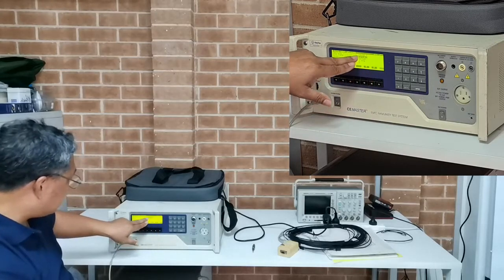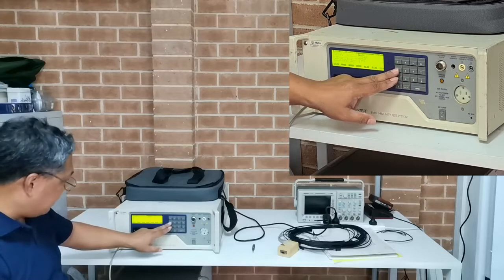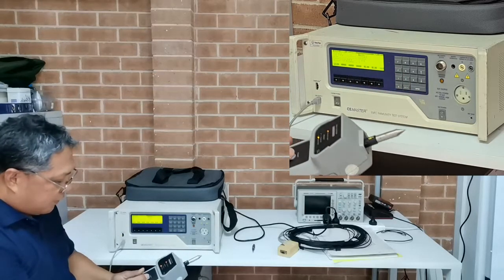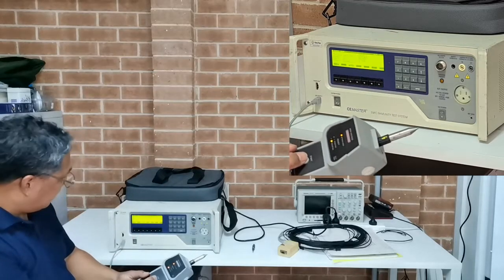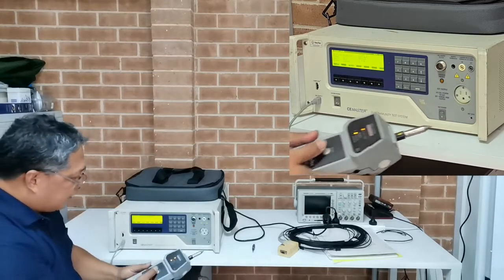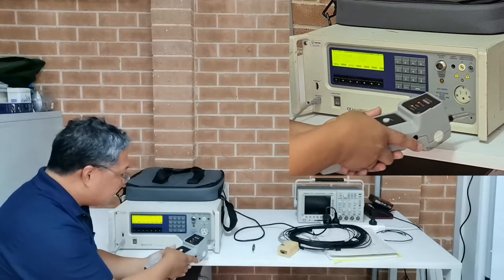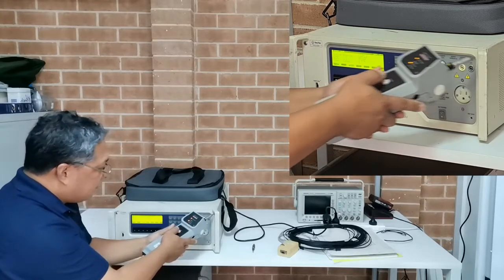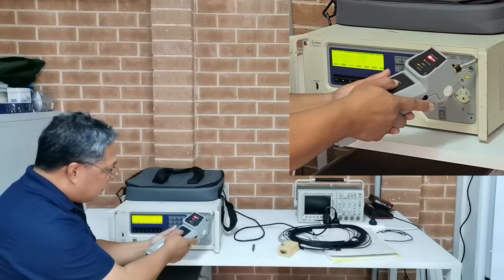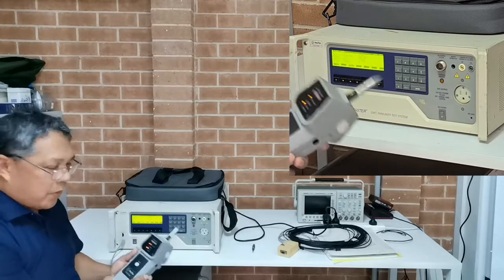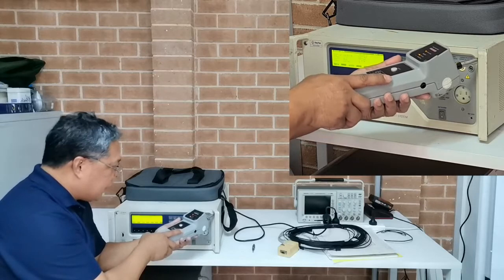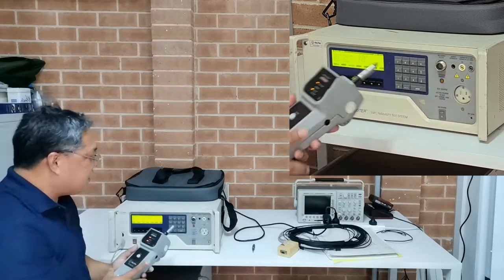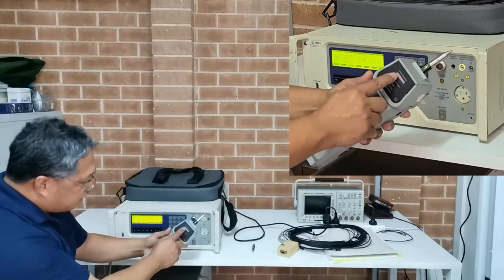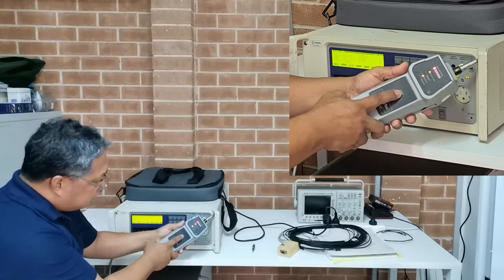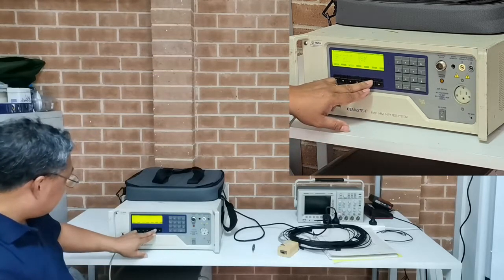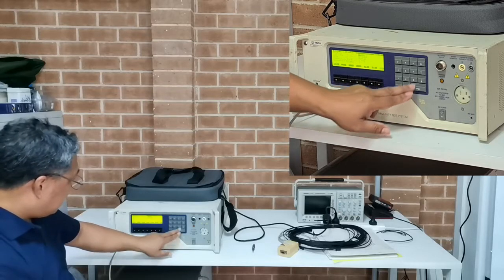So the maximum of this one, we have 4 kV, so we should be fine. Okay, sorry, we have to press run and then press that button. To do contact discharge, normally you have to apply the tip onto the contact point here, then press the button. But I didn't, so I guess I have to press the one and then do it like that. But the standard requirement is you have to hold the tip right onto the contact first before we apply the high voltage, and I think it does that, because you can see the high voltage jump and then it discharges. Yeah, it does.